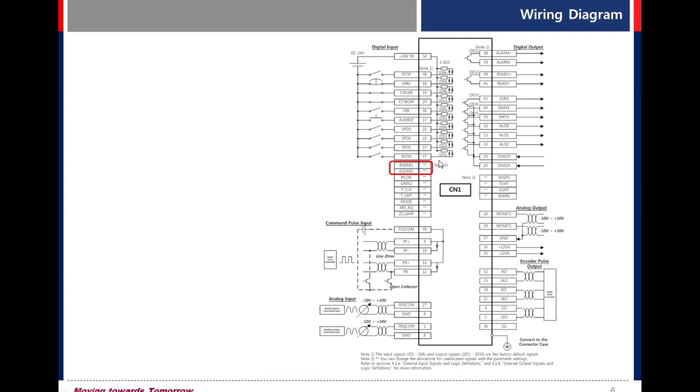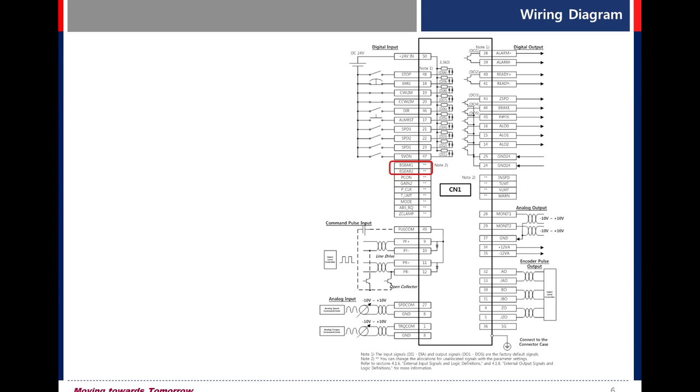This signal means the default value is not assigned, so to use these functions you must assign first. Electronic gear ratio 1, 2. Possible to change electronic gear through this digital input. Through combination of those digital inputs, you can use four different types of electronic gear ratio.